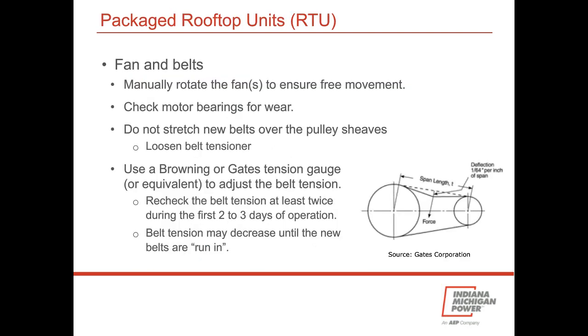And so you really want to go and check your fans when they're off and power's off. Rotate the fan, make sure it can move freely by manual intervention. Check bearings. Loosen the belt tensioner when you're putting new belts on. Don't stretch them over the sheaves using a screwdriver or whatever. And then use an appropriate belt tension device, a Browning or Gates tension gauge. And you're going to have to do that when you first put the new one on, probably a couple of times during the first 2 to 3 days because they'll stretch just a little bit. And you want that optimum pressure on that.